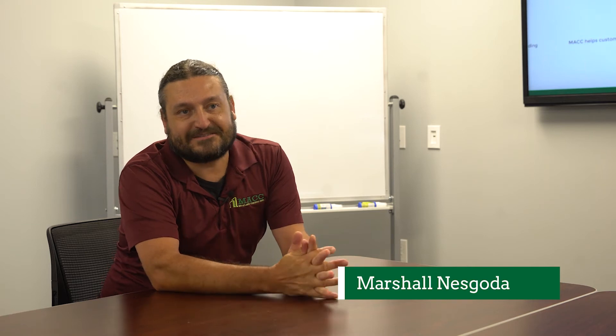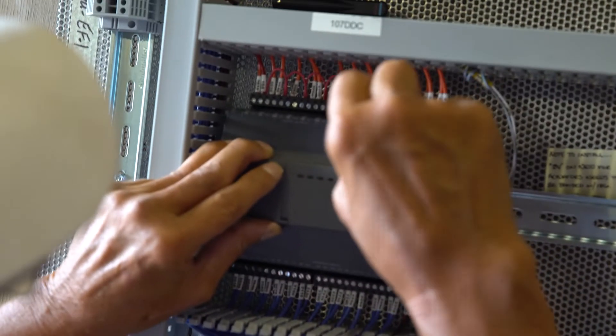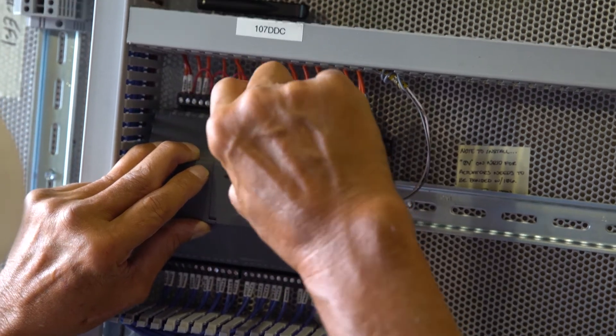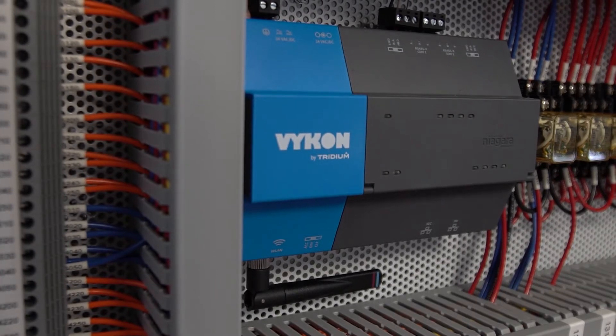What will impact the cost of the BAS system? That's going to be answered by more questions: Is this a new building or is this a retrofit? Is there an existing control system or are we starting from scratch? That ranges anywhere from $2.50 a square foot to $7.50 a square foot. It varies very much with the criteria you have to meet — for example, stringent alarming and long-term data history requirements, like FDA requirements that can require you to hold seven years worth of data.